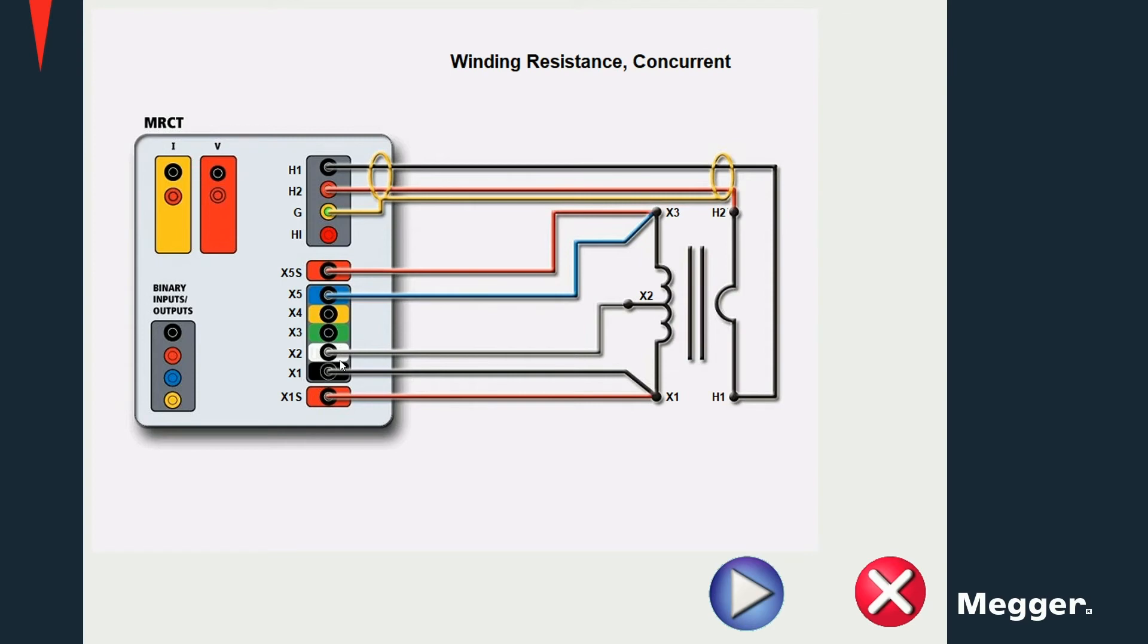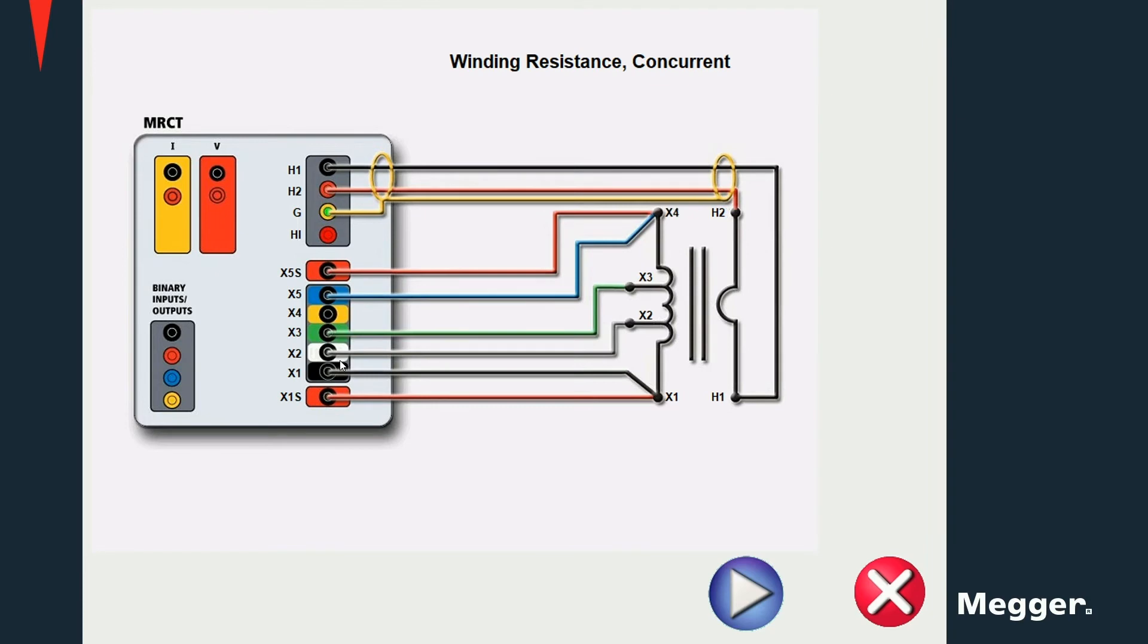For a three-tap current transformer, connect the X1 and X5 terminals to the main tab, X1 and X3, and the X2 terminal to the second tab. Similar connections apply for a four-tap current transformer. X1 and X5 should always be connected to the main tabs, X1 and X4 in this case, and the other terminals to the corresponding tabs on the current transformer.